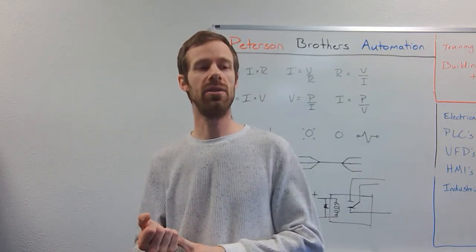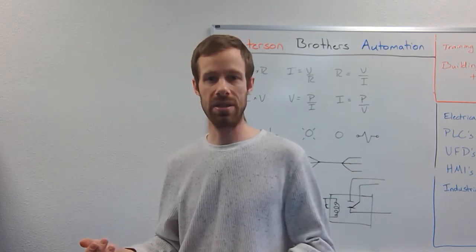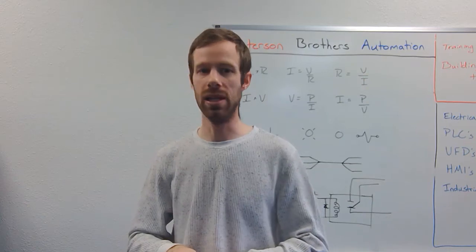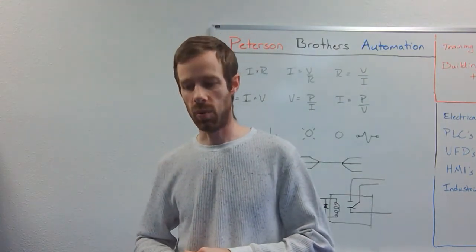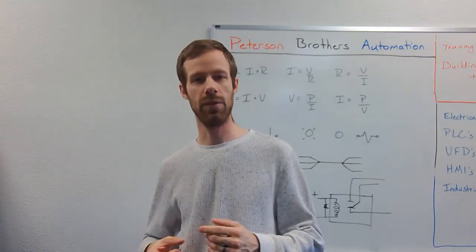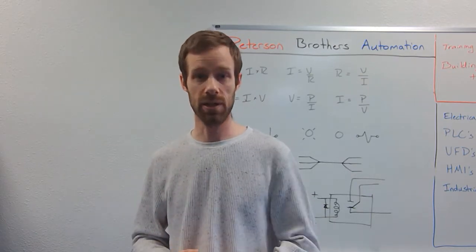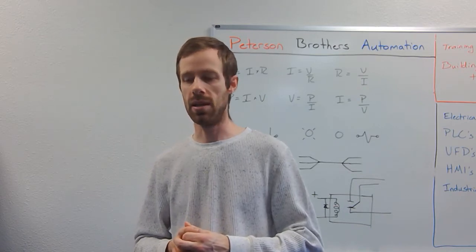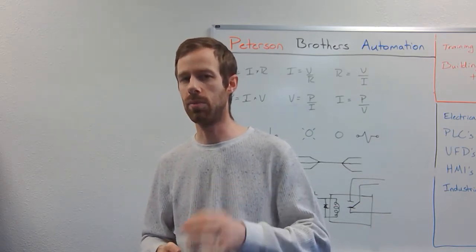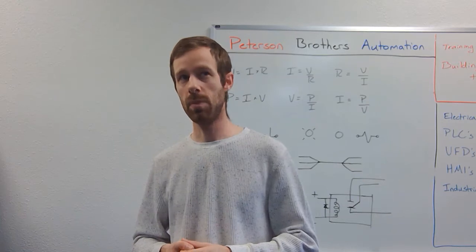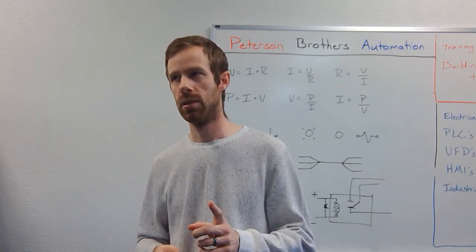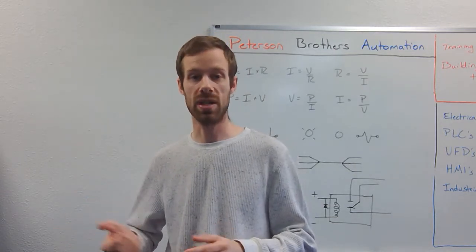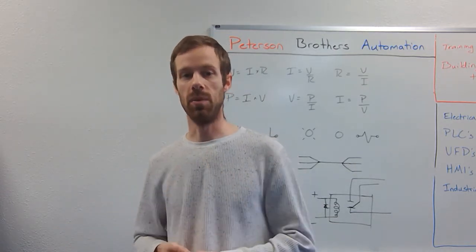If somebody rewired your house and they tried to save a little bit of money and used wires that are a little bit too small, be really careful about that. Because when wires are too small, even just one gauge size different, that can cause a lot of extra stress. And all you need is somebody plugs in one light bulb too many, and it may not be enough to trip the breaker. It may just be enough to really overheat that wire and the appropriate size of the connections. That's when we run into problems.